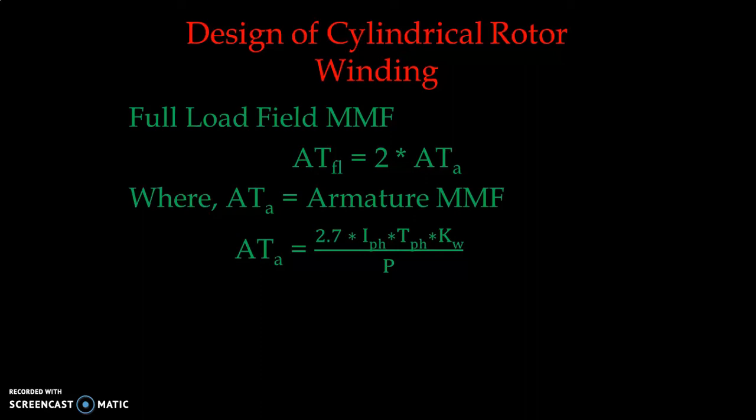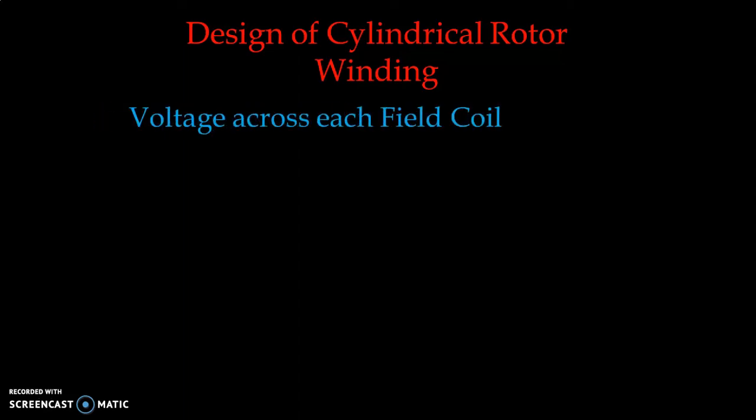Once the armature ampere-turns are available, we can calculate the MMF of the field winding. Now, the voltage across each field coil — Ef — is given by 0.8 to 0.85 times the excitation voltage Ve, divided by the number of poles P.